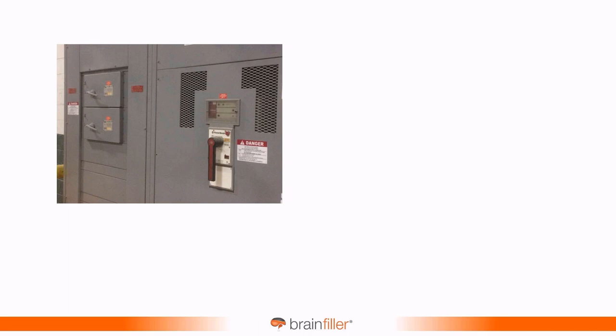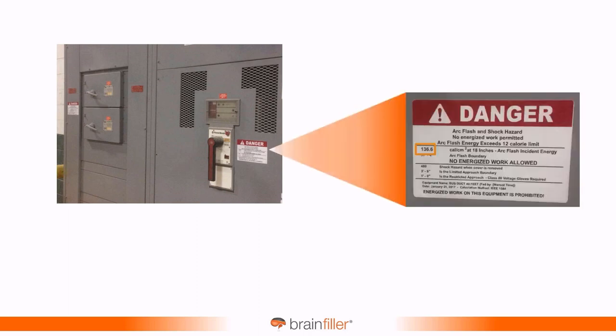This might look familiar for some of you. If you look closely at the label, we have an incredibly high incident energy. This is an age-old problem. This one, it's over 130 calories a square centimeter. I'm sure many of you have run into this. Normally, what causes such incredibly high levels of incident energy is the arc duration. It's not that the arc would last like forever, but the calculations will sometimes indicate that.